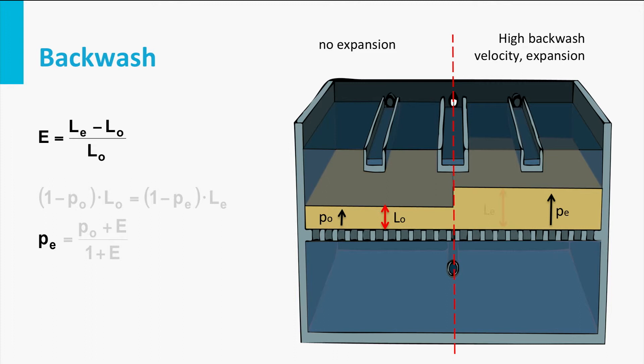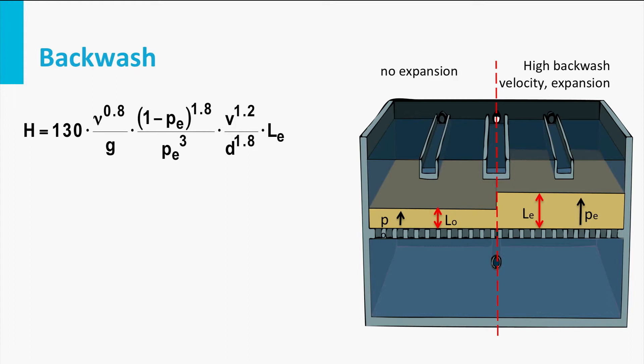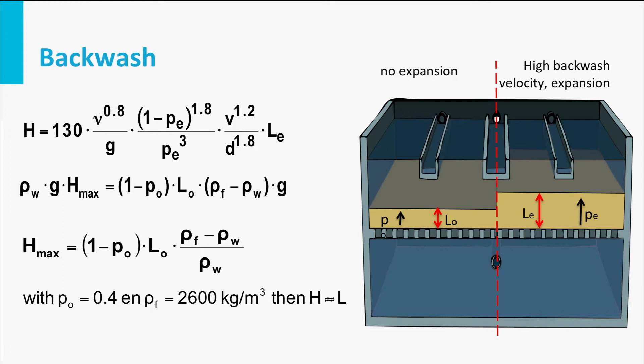To determine the resistance during backwashing, an empirically determined equation can be used, resembling the Carman-Kozeny equation. When fluidization is reached, the pressure drop equals the submerged weight of the filter bed and remains constant with increasing backwash velocity. For sand, expressed in meters water column, this equals the filter bed height.